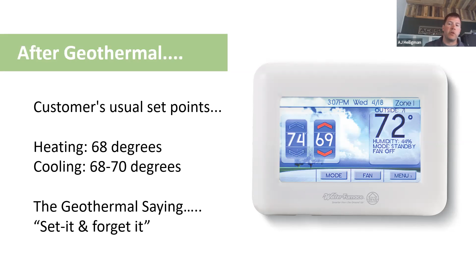It shows we're supplying air at 57 degrees in this live snapshot, and his compressor is on speed 1 out of 9 or 12 speeds. Pretty impressive. His loop field temperature right now is 45.3 degrees, which is super efficient for the beginning of the cooling season, as it's still recovering from winter. He's keeping it at 68 degrees for 122 watts of compressor energy, so basically 2 light bulbs are what's cooling his house this morning.